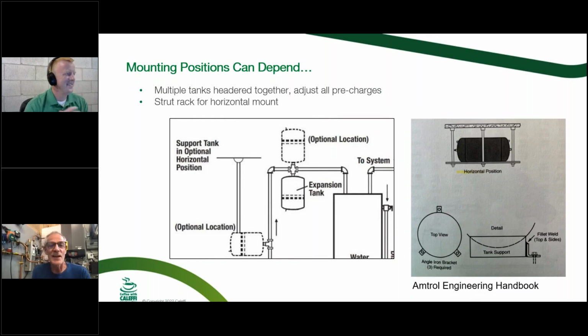Yeah. The other question that comes up a lot, and again, I don't know that I have an exact answer to this, is can I mount a tank other than nipple up, under wherever you're going to mount the expansion tank on a fitting, like we showed on those previous slides. And this is right out of one of the manufacturer's installation manuals, which I did get permission to use. And it says the preferred method is with the nipple up, hanging down like you see in the bottom of the center, the first drawing there. It does show an optional location with a nipple down and the tank up.